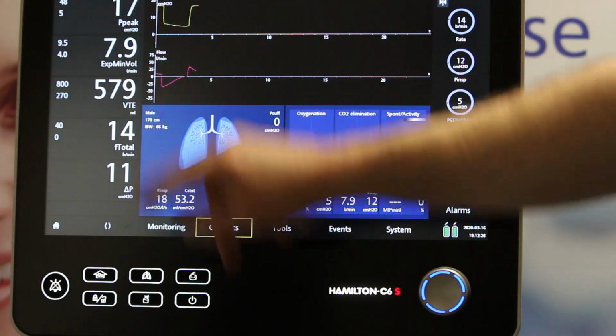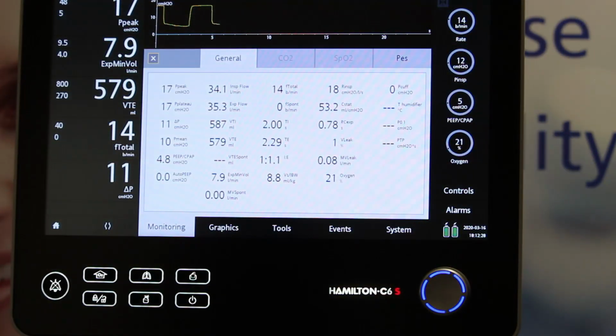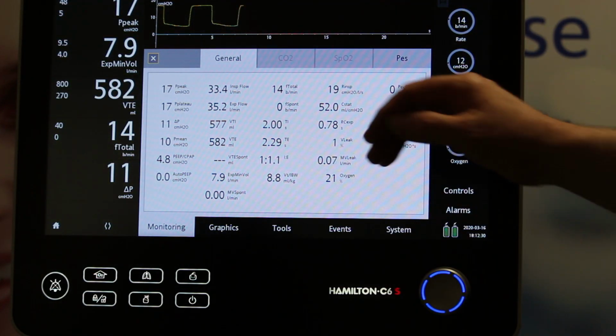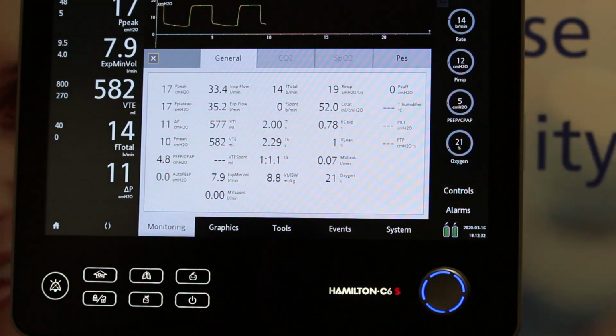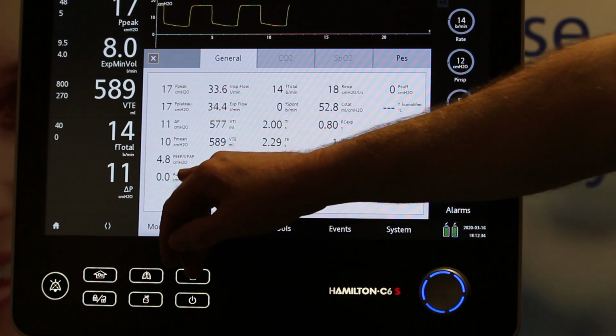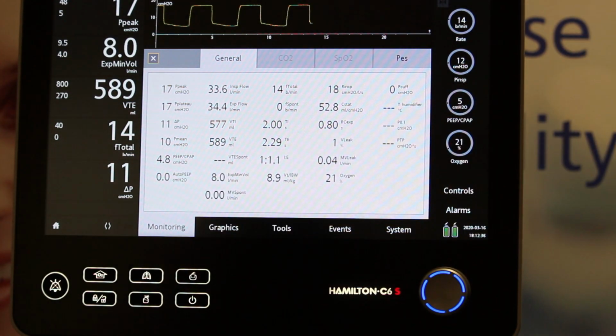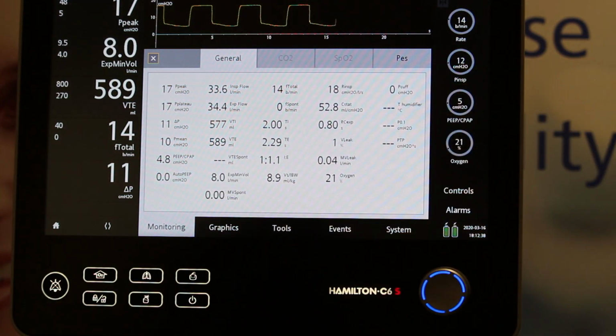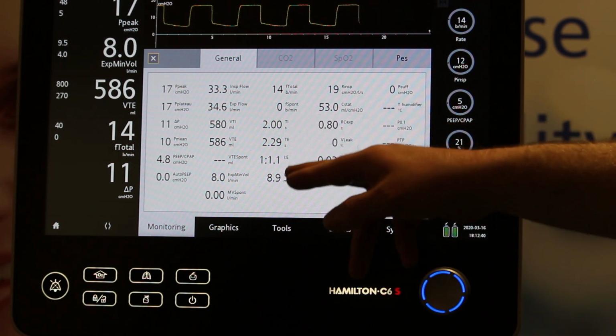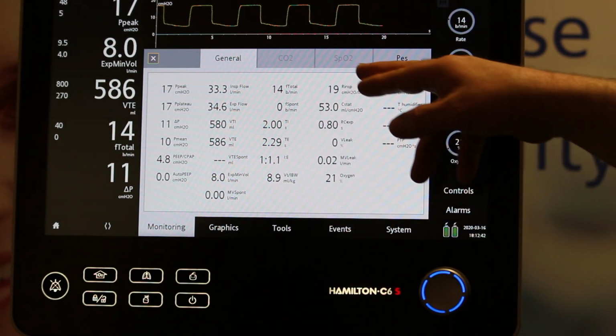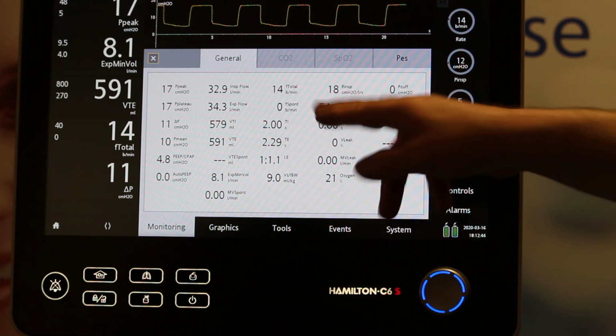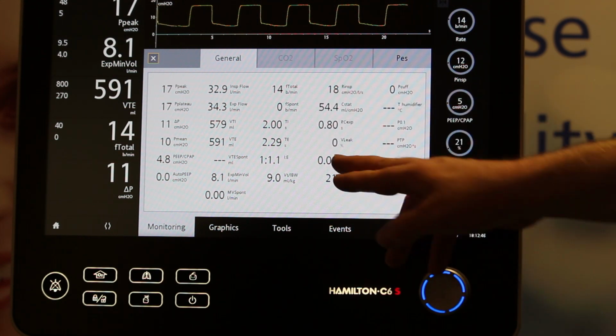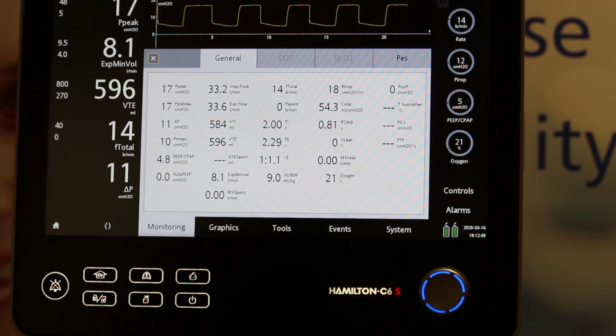My main monitor parameters are here, and if I go into monitoring, these are all the monitor parameters. So you can see we've got a plateau pressure, we've got our driving pressure, we've got our PEEP, our auto PEEP here as well, I&E flows. There's my minute volume, I&E times, mils per kilo, resistance, static compliance, the time constant, how much leak is in the circuit, and that's all in monitoring.